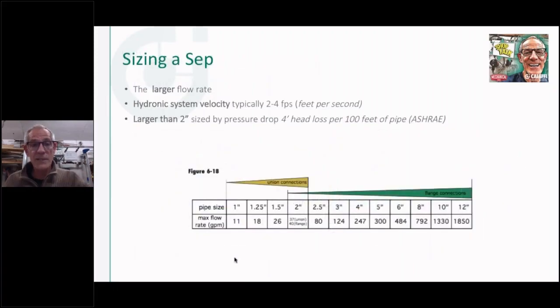And we'll go back to this here. So let's say I've got a load, I'll pick a number, say 25 gallons per minute. I would just go and say, okay, 1.5 inches would give me the 25 gallons a minute. Now we do have a little bit of wiggle room in these, and you can call us if you've got a job that says, I need 30 gallons a minute. Do I have to go up a size? Call tech support.